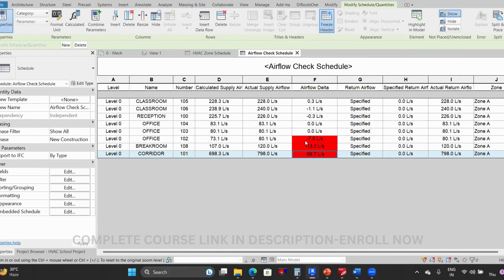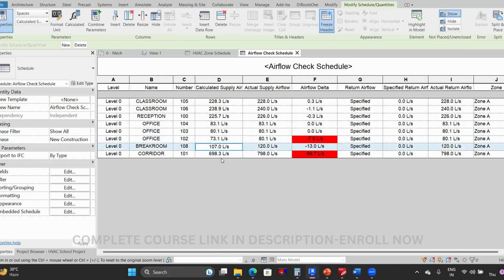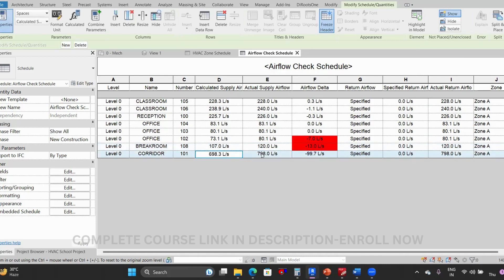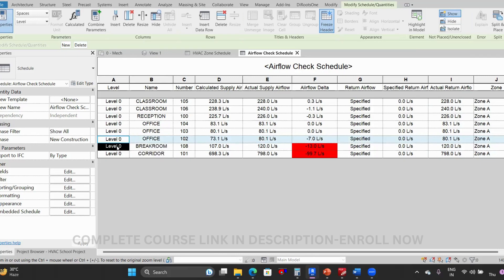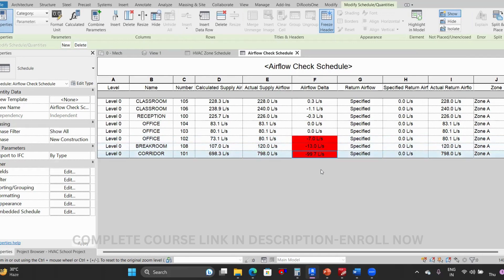Now you can see there is a big difference in some spaces — for example, minus 7: the actual value needed is 73, but 80 is being supplied. Another space needs 107 but 120 is supplied. One space needs 698 but 798 is supplied. In these three spaces I have to change the values so the red indicator will not appear. When you have 20, 30, or 40 spaces this automatic highlighting is very helpful to identify which space has a higher or lower flow rate.